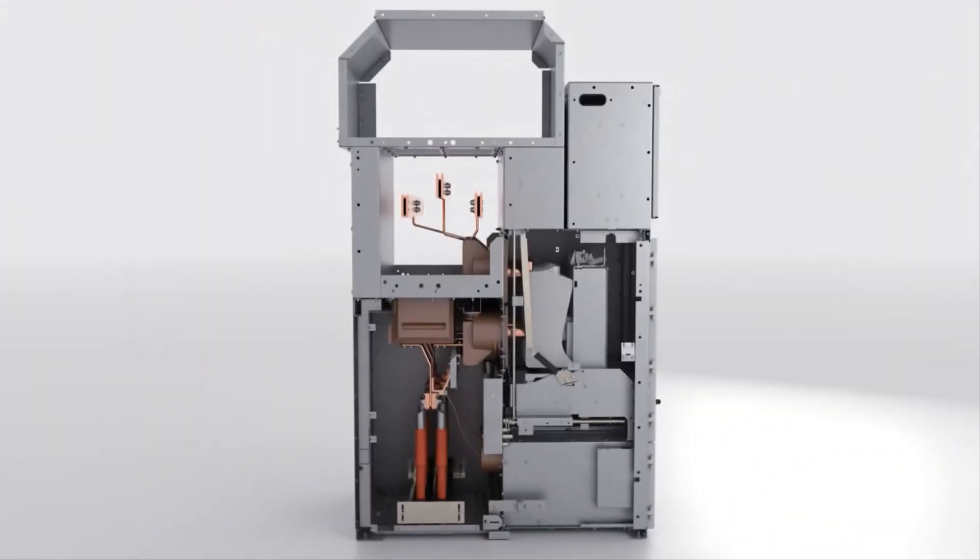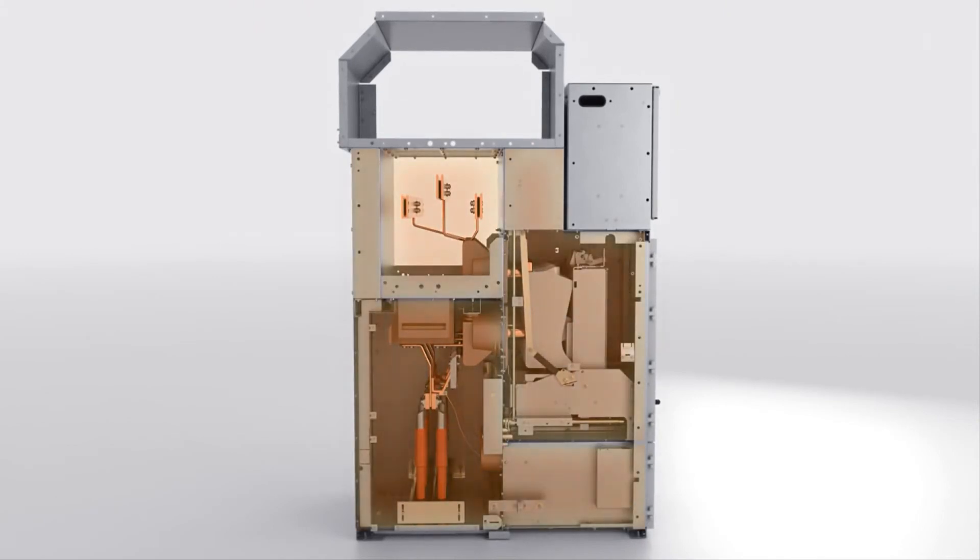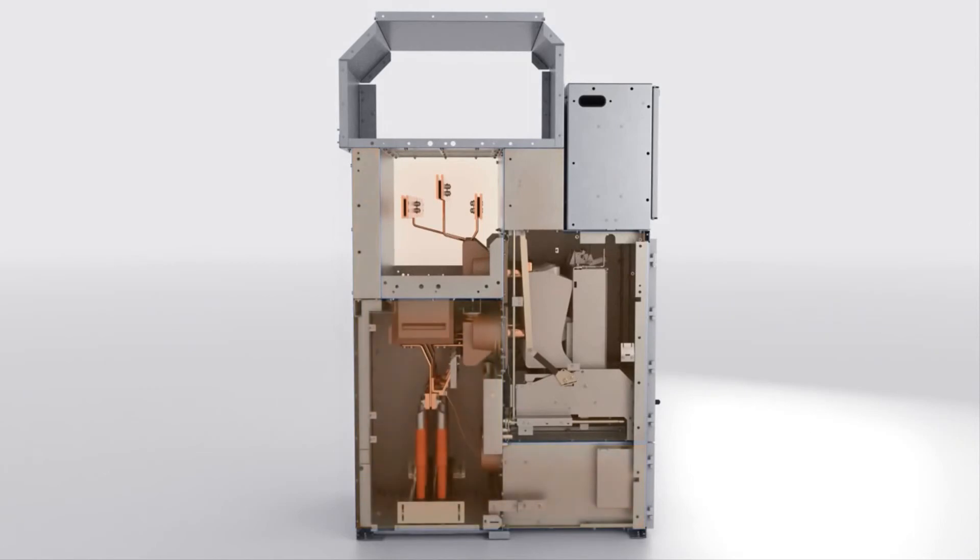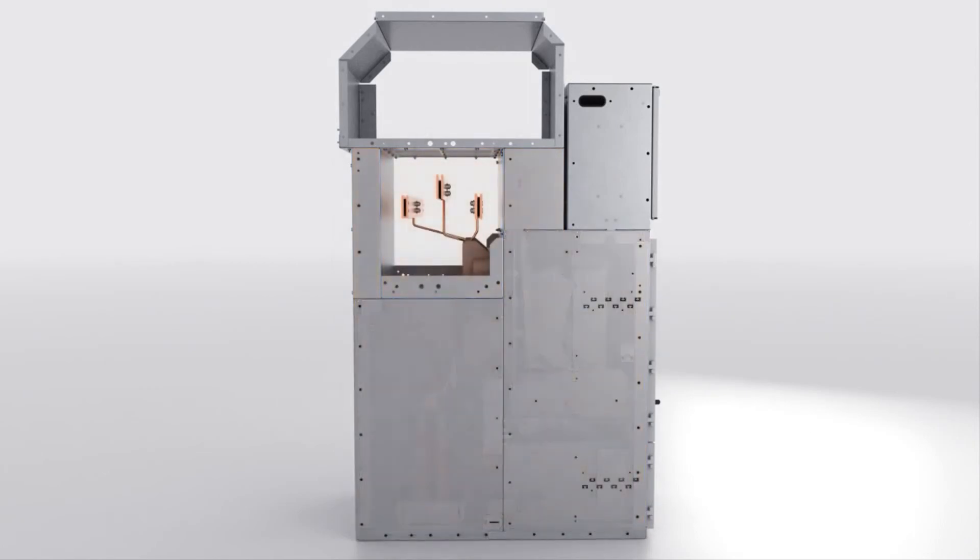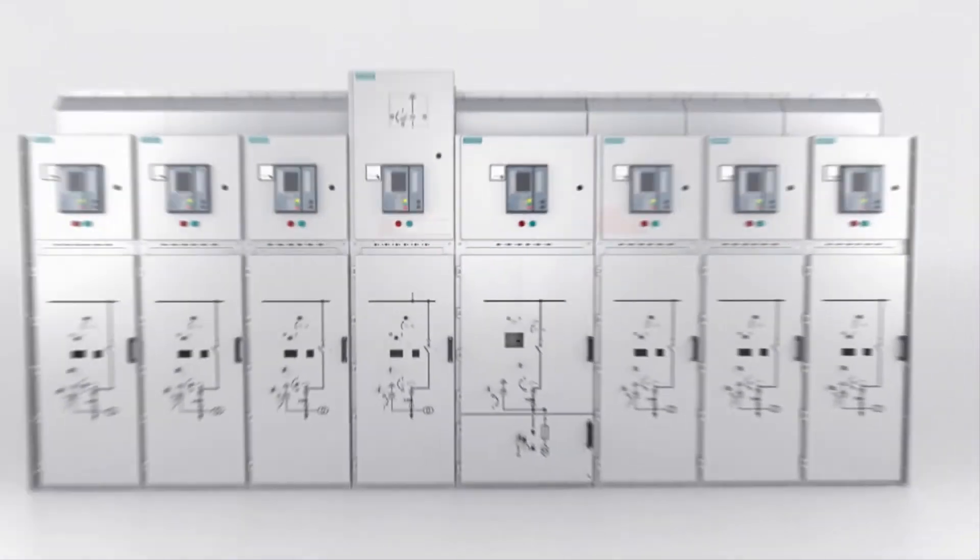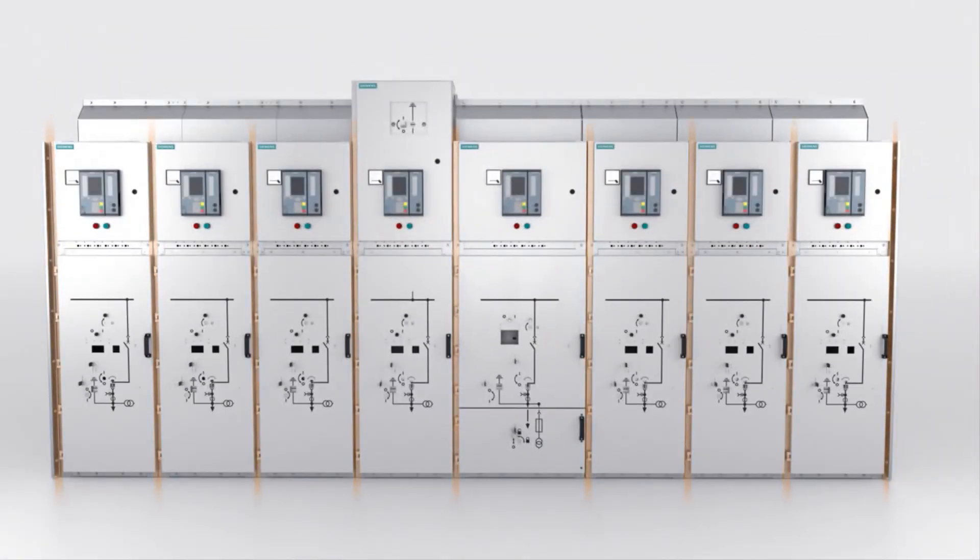NX-Air withstands internal arc faults of up to 50 kA for one second. Metal partitions ensure localization of internal arc damage within one compartment, which is beyond standard requirements. This guarantees high availability of the switchgear.